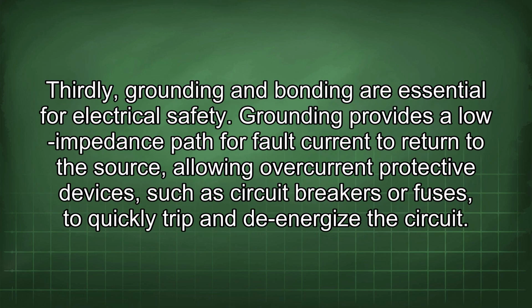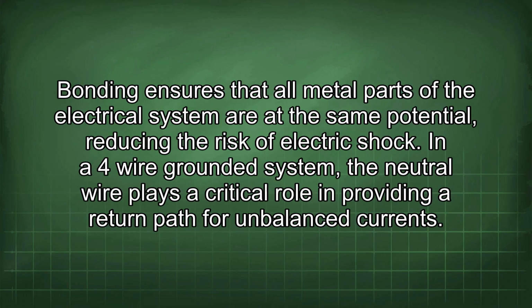Thirdly, grounding and bonding are essential for electrical safety. Grounding provides a low impedance path for fault current to return to the source, allowing overcurrent protective devices, such as circuit breakers or fuses, to quickly trip and de-energize the circuit. Bonding ensures that all metal parts of the electrical system are at the same potential, reducing the risk of electric shock.